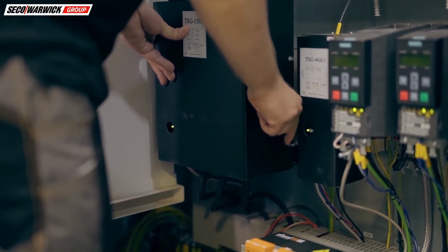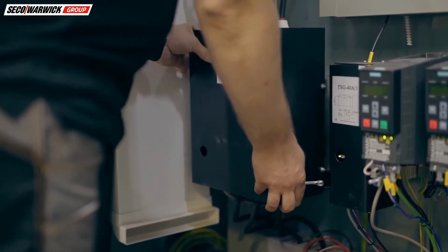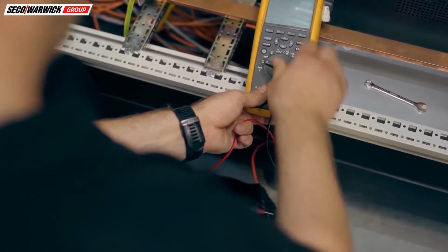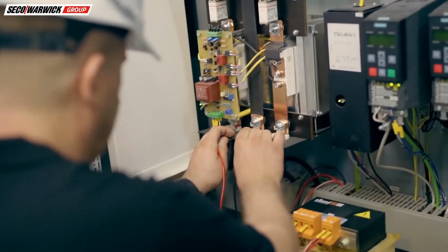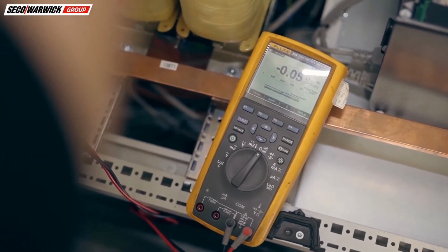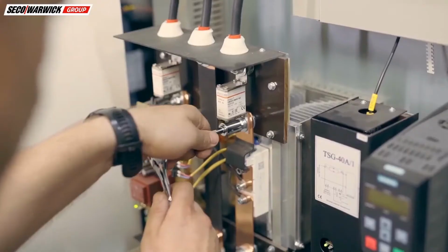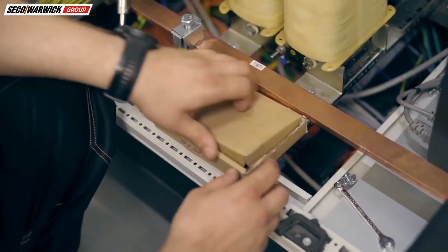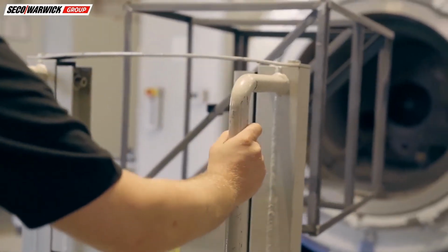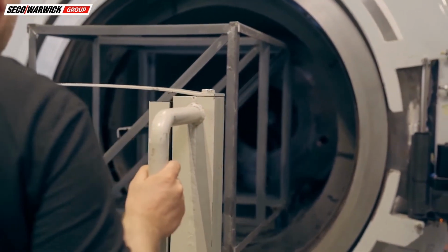In this type of horizontal furnace, heating elements are made from spirally wound resistance wire placed on ceramic pipes. The thyristor or heating controller installed in the control cabinet provides power to these heating elements as called for by the 4 to 20 milliamp signal from the output of the PLC for each individual heating zone. The condition of the entire furnace heating system can be checked on the industrial computer through WinCC-based control software. After checking the heating system and the relevant parameters, the root cause of the issue is quickly located and corrected, allowing the service engineer to restore heating to normal operation.